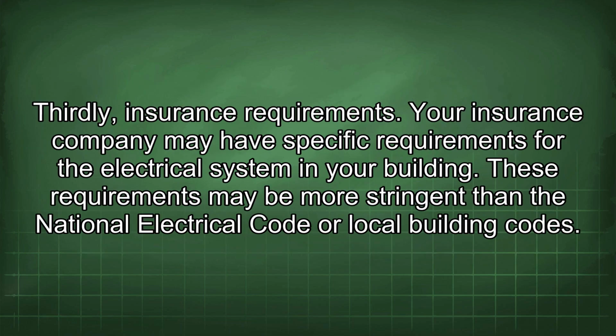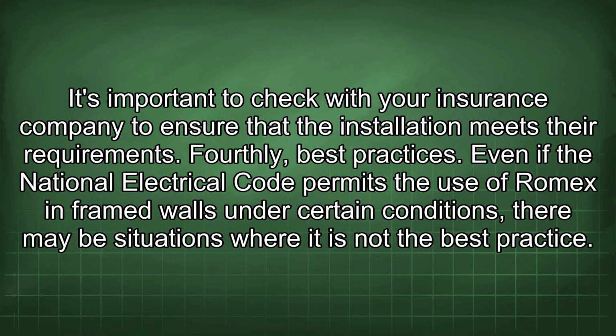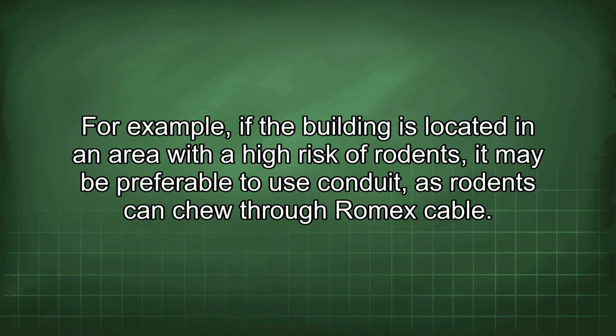Thirdly, insurance requirements. Your insurance company may have specific requirements for the electrical system in your building. These requirements may be more stringent than the National Electrical Code or local building codes. It's important to check with your insurance company to ensure that the installation meets their requirements. Fourthly, best practices. Even if the National Electrical Code permits the use of Romex in framed walls under certain conditions, there may be situations where it is not the best practice. For example, if the building is located in an area with a high risk of rodents, it may be preferable to use conduit, as rodents can chew through Romex cable.